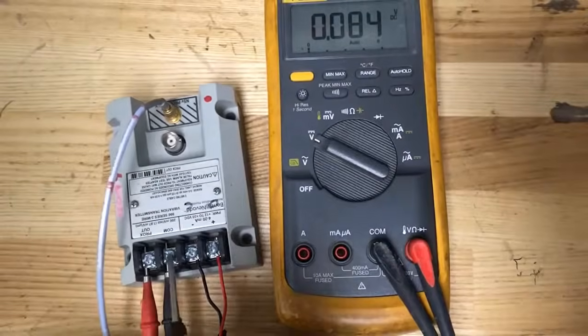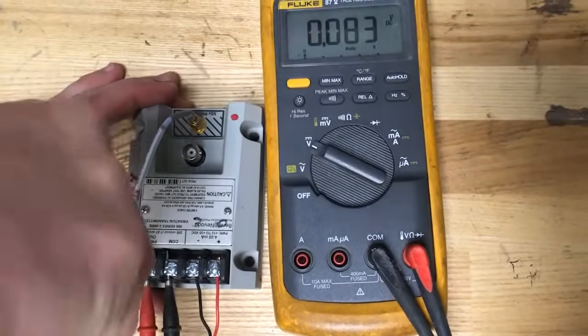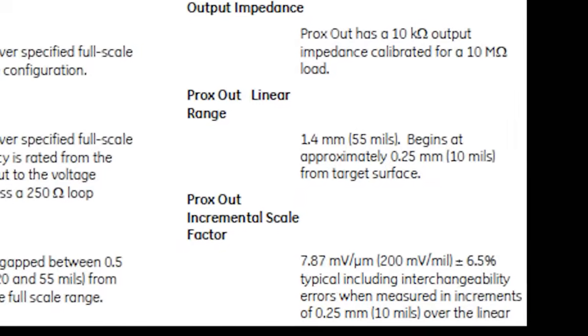Place the multimeter test leads on the terminals, which represent the gap voltage. To determine the proper gap voltage setting, you will have to refer to the spec sheet of the proximity probe you are testing.